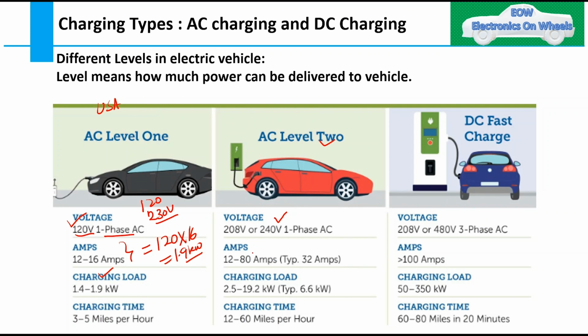In that case the amps can go up to 80 amps maximum, typically 32 amps is used. If I calculate the charging load, 240 into 80 amps gives you 19.2 kilowatts. This is the maximum value you can take from the charging station, and this is what we define as the level, how much power can be delivered to the vehicle.